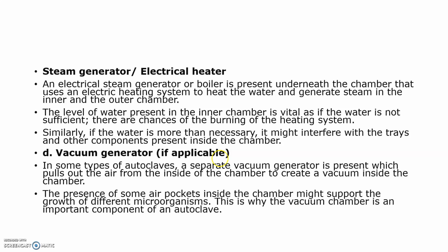The next is the steam generator or electrical heater. The electrical steam generator or boiler is present underneath the chamber and uses an electric heating system to heat the water and generate steam in the inner and outer chamber. The level of water present in the inner chamber is vital, because if the water is not sufficient, there is a chance of burning of the heating system. And also, if the water is more than necessary, what happens? It might interfere with the trays and other components present inside the chamber.